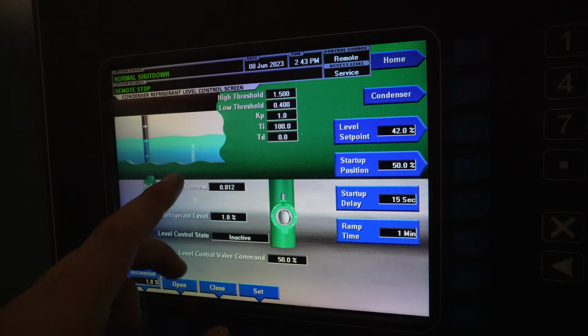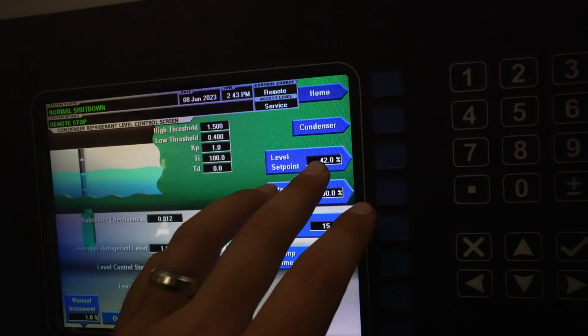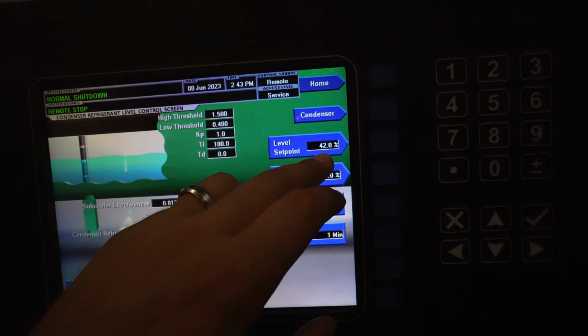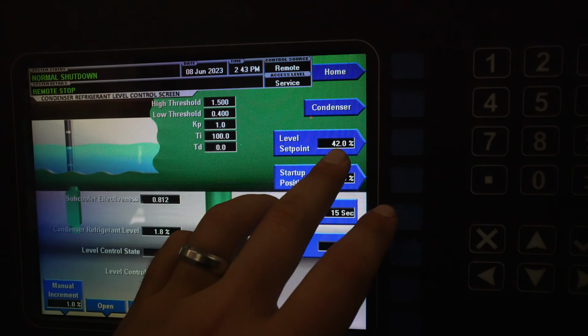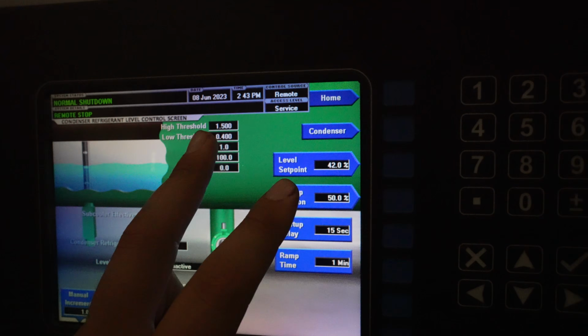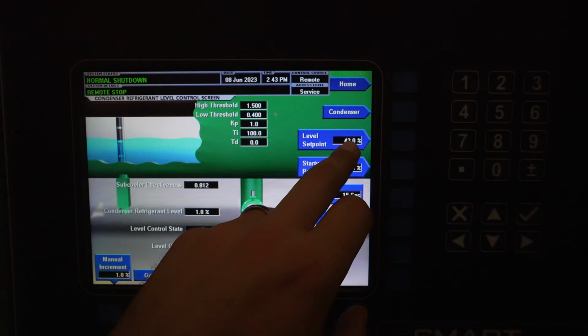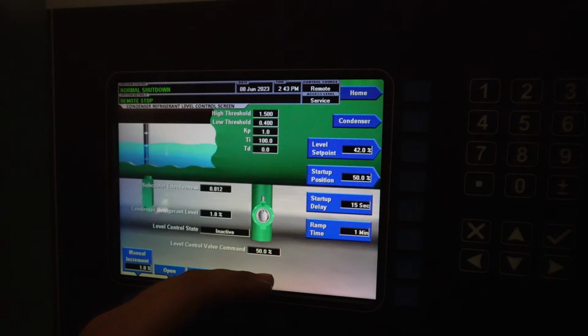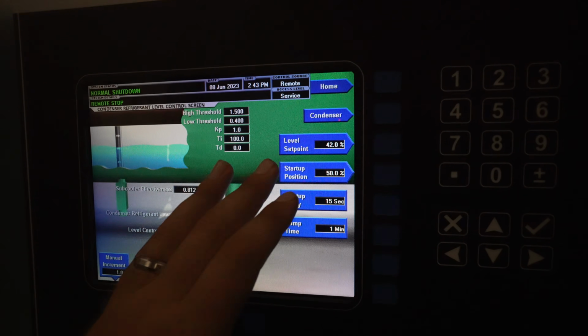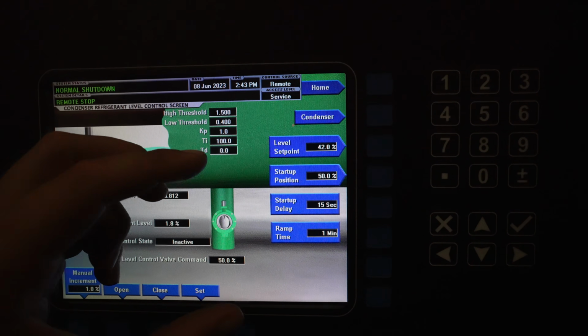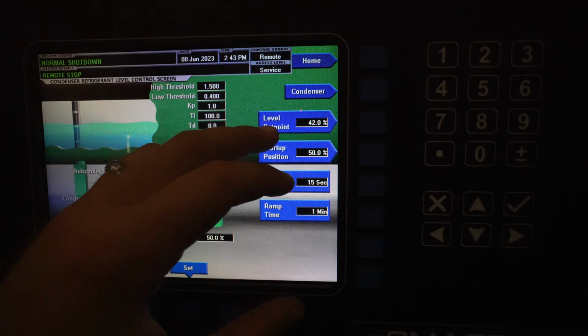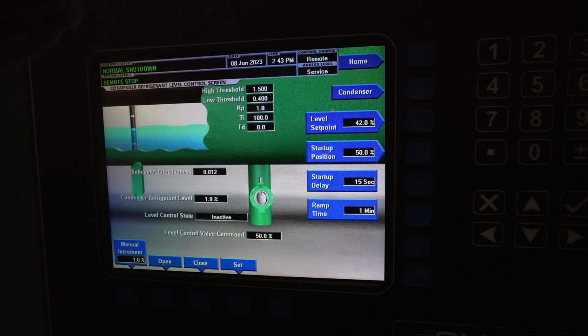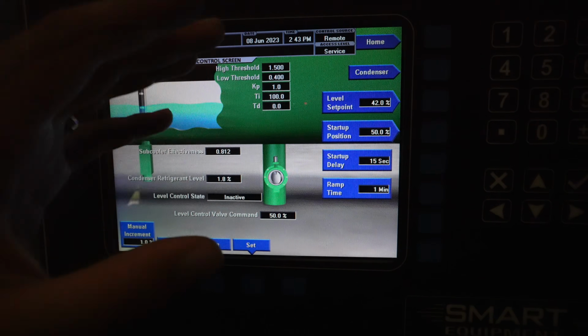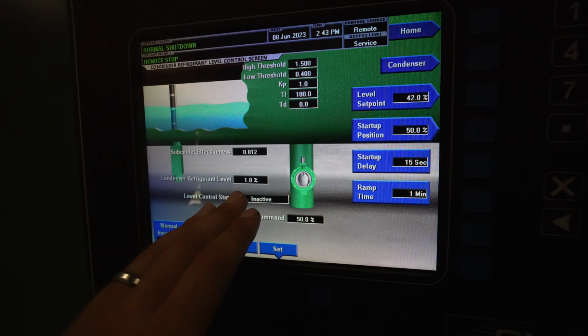By me coming into the level control, and how I did it is I bumped this up with it running. I bumped this up 2% at a time until I got to 42. So by the time I hit 40% from 35, I was at about half an inch above the subcooler plate, and then another 2% got me right at that 3/4 of an inch to 1 inch mark. It was spot on perfect. The machine was holding it.